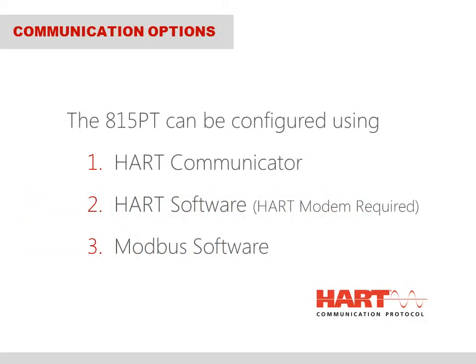There are three ways to configure, diagnose, or reconfigure the 815 PT. One may use a HART handheld communicator, or HHC. The HHC is considered a HART master. Another option is to use a computer with HART configuration software and a HART modem. The HART software and modem are readily available from many suppliers. The modem simply plugs into a USB port on any computer. The modem is also considered a HART master.